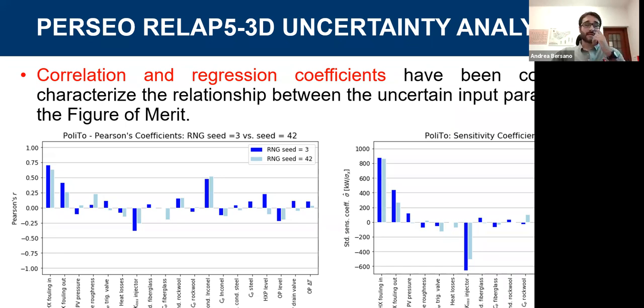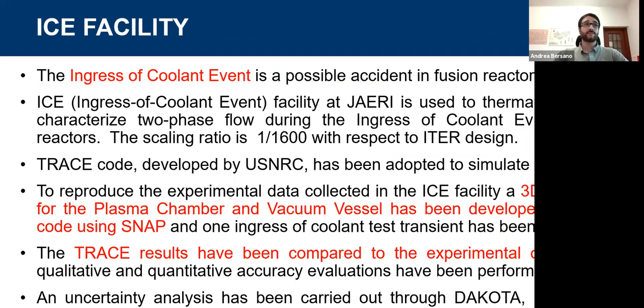Then we did a second application. The first one, as I already mentioned, was related to the decay heat removal system, basically for fission application. And we also did a second application to see if this methodology is applicable also to a passive system devoted to fusion application. In particular, we considered the ingress of coolant event, that is a possible accident in fusion reactors. And in Japan, at JAERI, there is a facility that was designed to study, to characterize from a thermal hydraulic point of view, the behavior of this event.